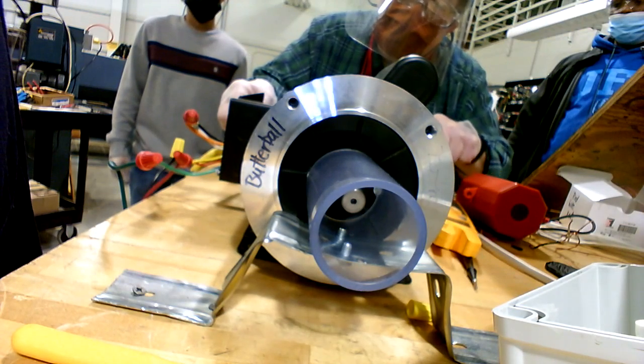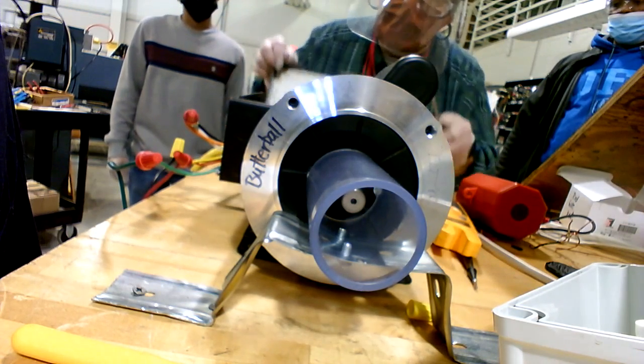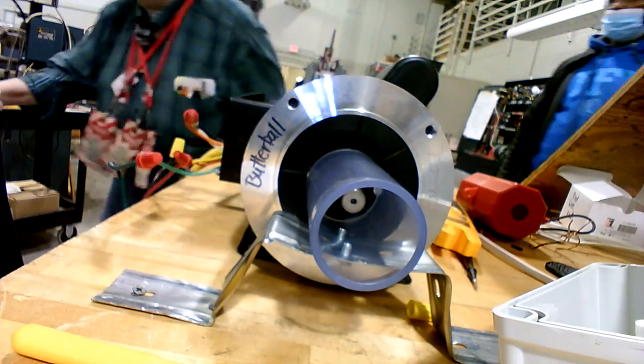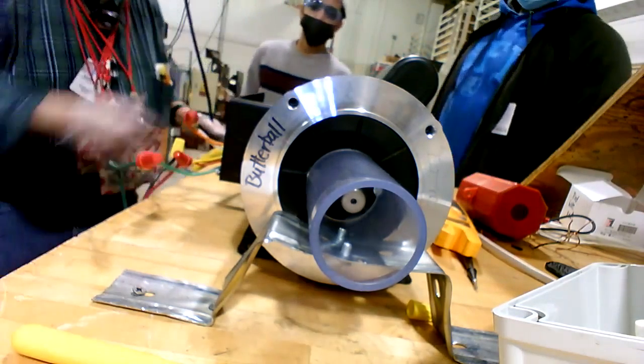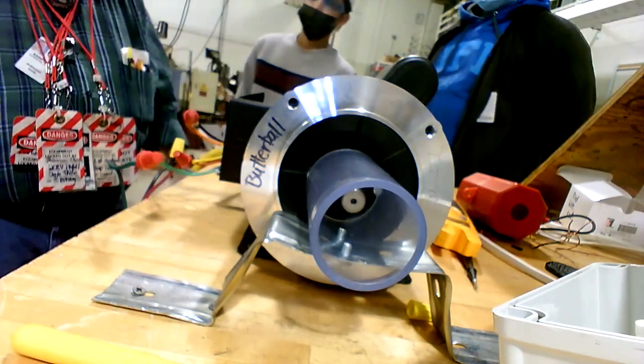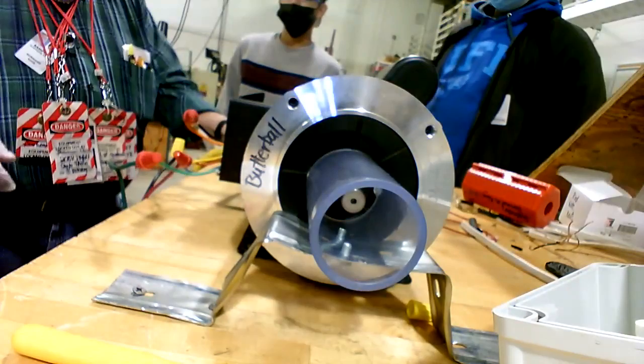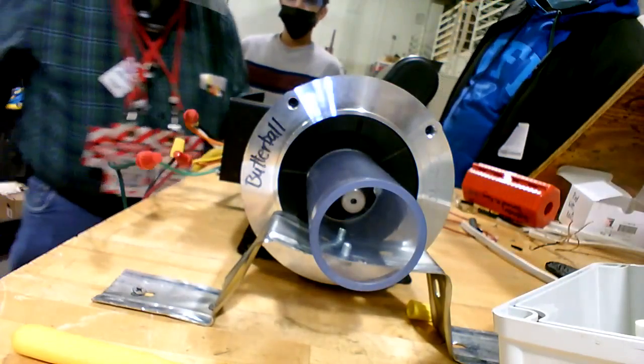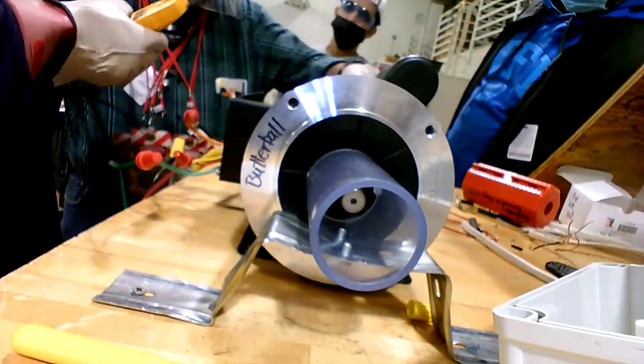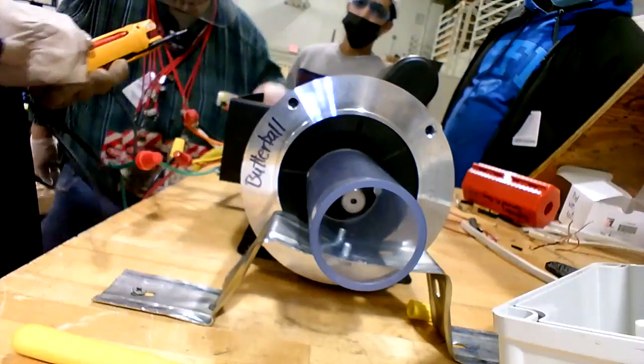There's an interlock there. We have to do that to get into a lot of them. Whatever the interlock is, you've got to override it to get into it. So this time you'll check the two incoming legs, leg to leg, and it should be around 208.